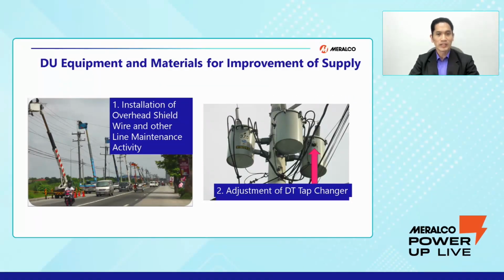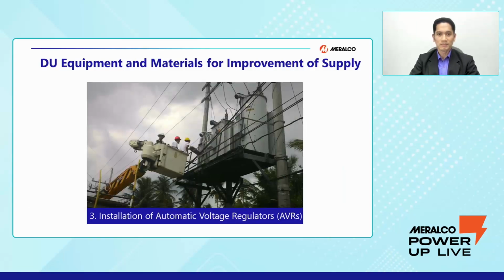And installation of overhead shield wire and other line maintenance activity is being done to prevent outages due to lightning, thunderstorms, and other events that might affect our supply voltage. And also the adjustment of our DT tap changer. And for the DU equipment and materials for improvement of supply, Meralco conducts voltage studies in areas where there are concerns about voltage. So we have to provide line AVRs like in this picture to further improve the voltage along the distribution lines. But most of the Meralco substations are already equipped with on-load tap changers. It means that at the substation level, the voltage is already regulated. Thus, installation of AVRs is minimal.